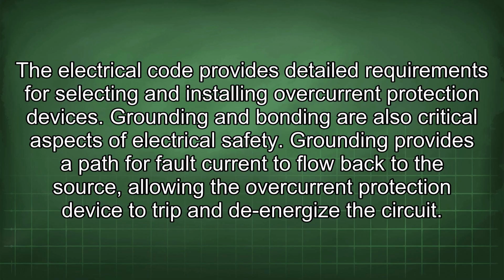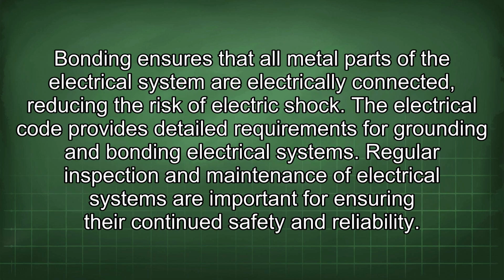Grounding and bonding are also critical aspects of electrical safety. Grounding provides a path for fault current to flow back to the source, allowing the overcurrent protection device to trip and de-energize the circuit. Bonding ensures that all metal parts of the electrical system are electrically connected, reducing the risk of electric shock. The electrical code provides detailed requirements for grounding and bonding electrical systems.